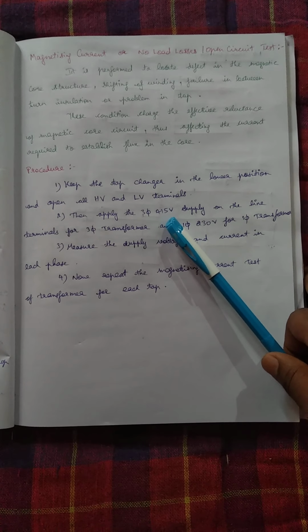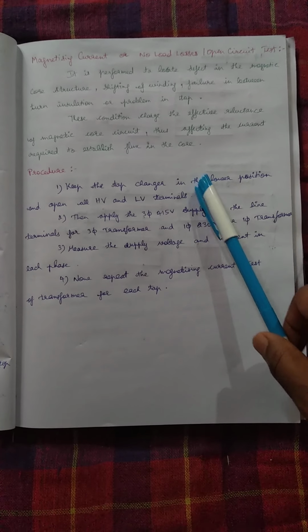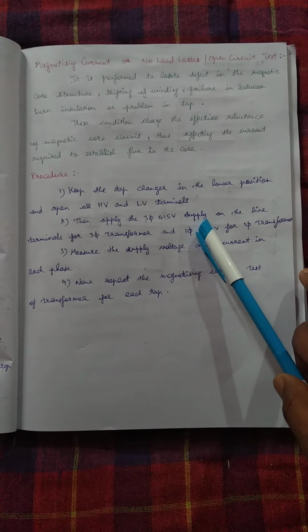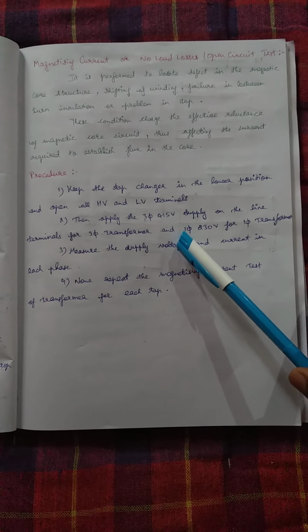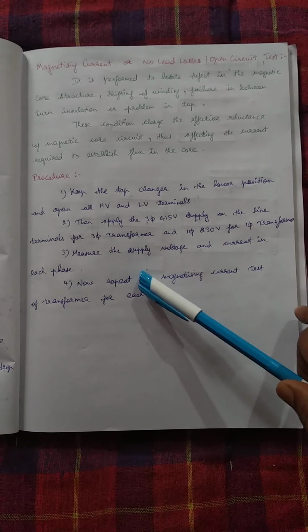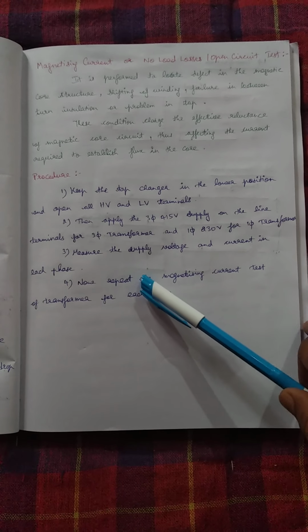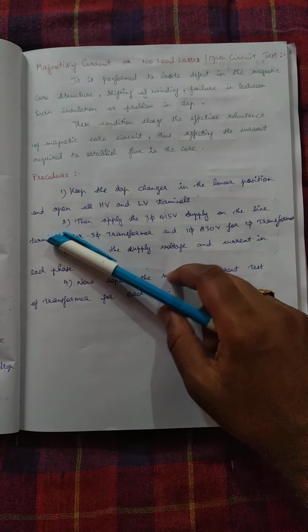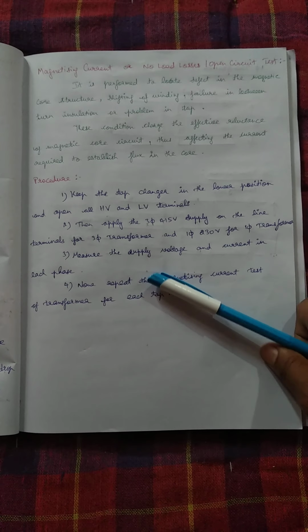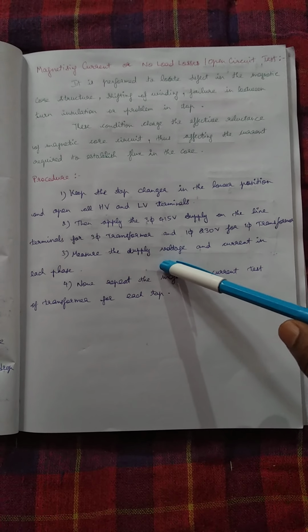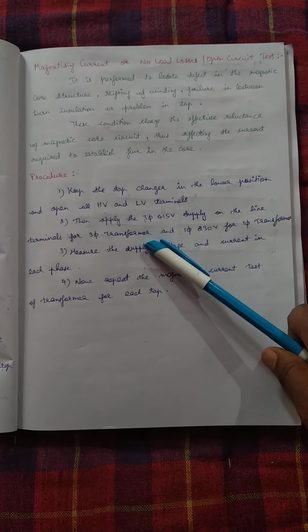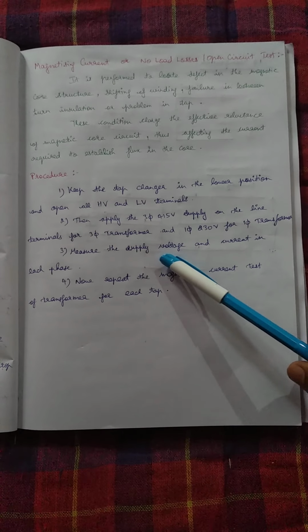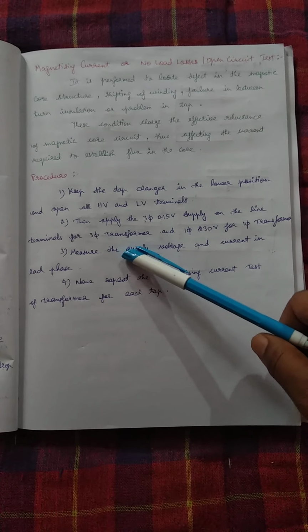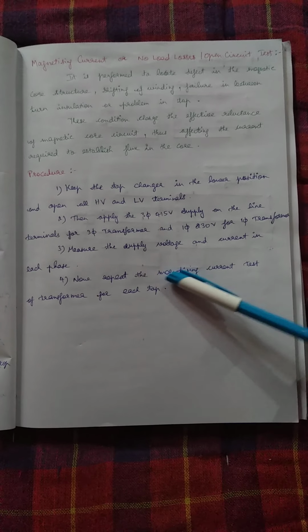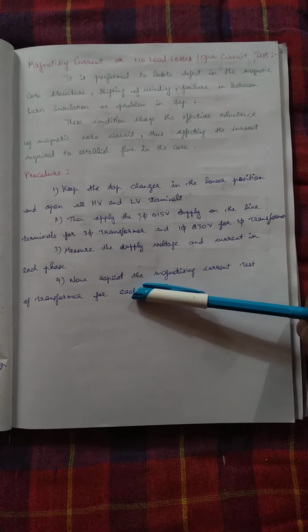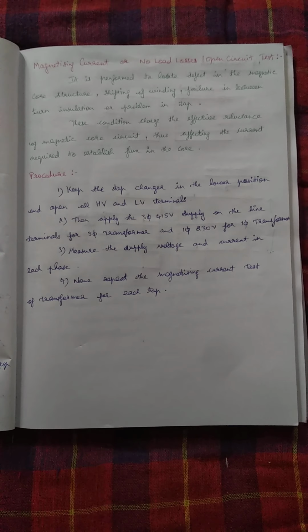After that, we need to apply a three-phase voltage to the primary of the transformer, or for a single phase transformer, we need to inject a single phase 230 volt supply to the primary, and then measure the supply voltage and current in each phase. For measuring the voltage, we will normally use a multimeter or any other voltmeter. For measuring the current, we will use a leakage tester or tong tester or even an ammeter. Now repeat this test for each tap. So this is the normal procedure for carrying out the no load or magnetizing current test.